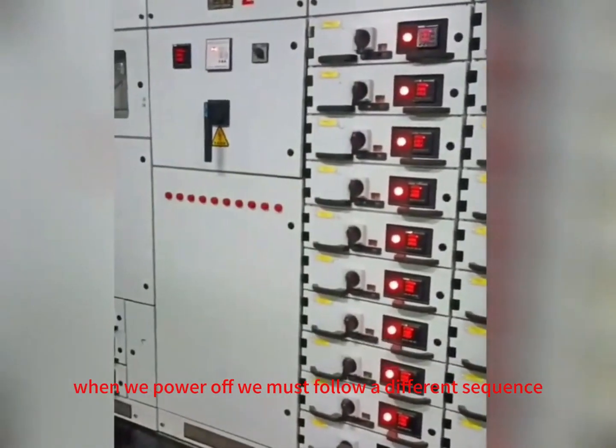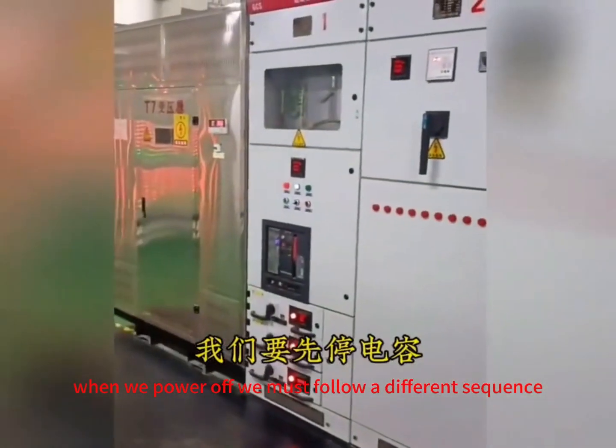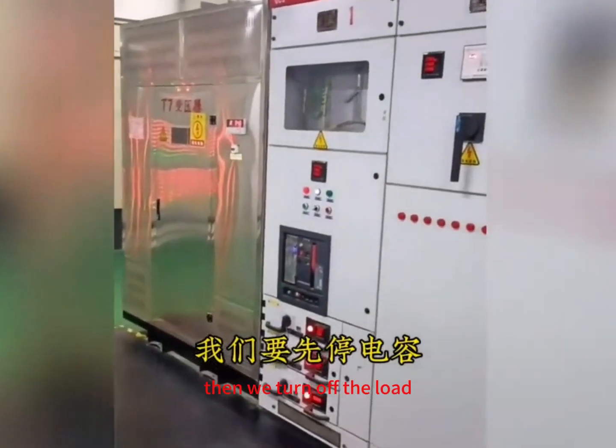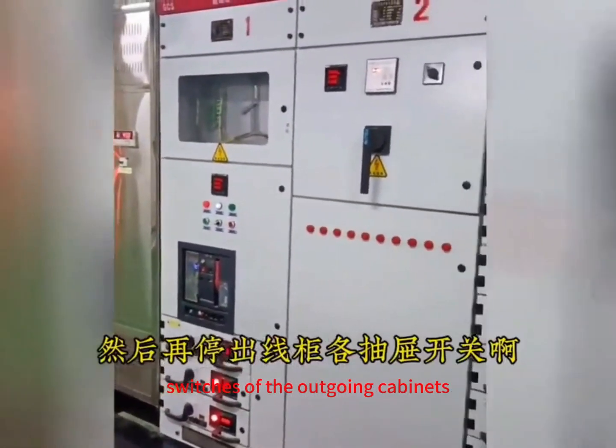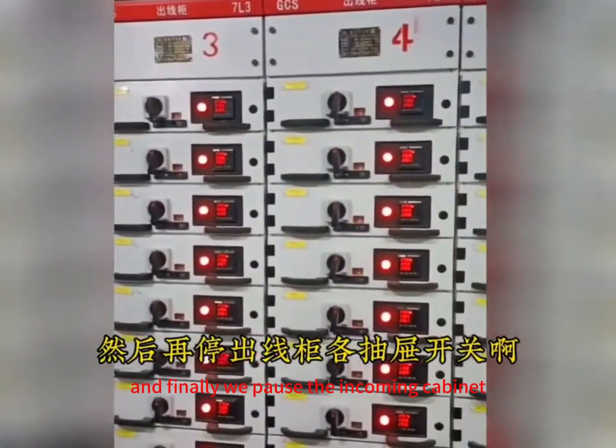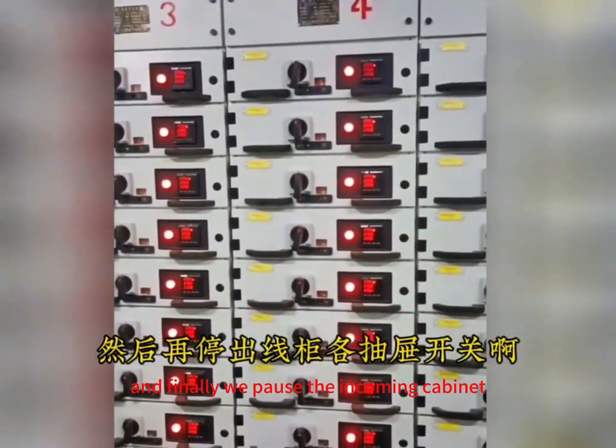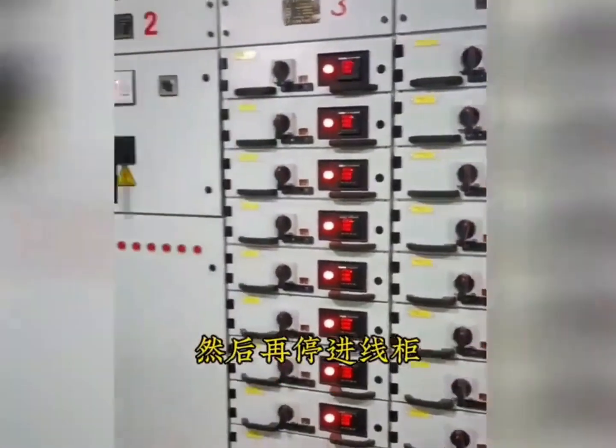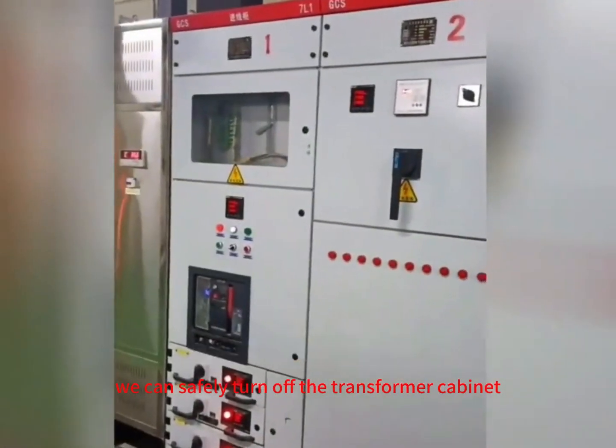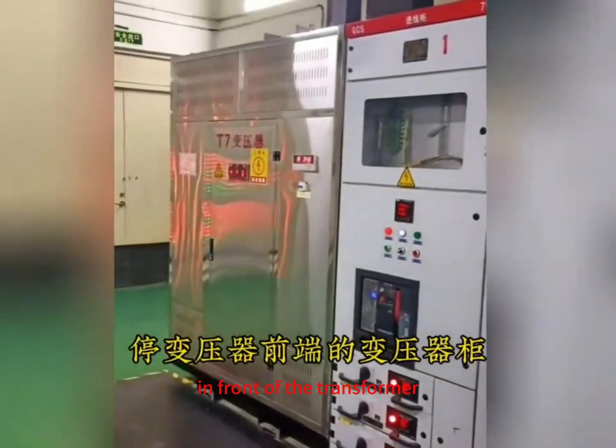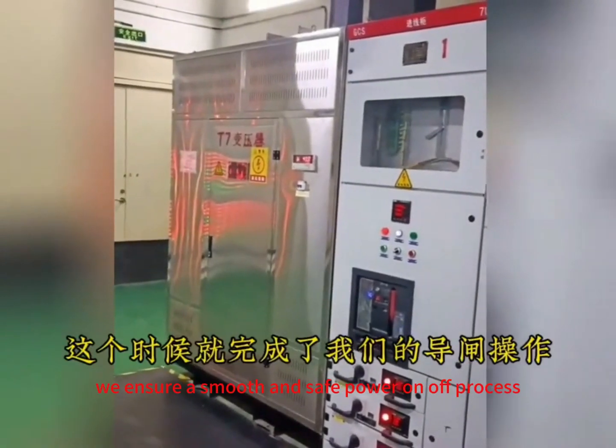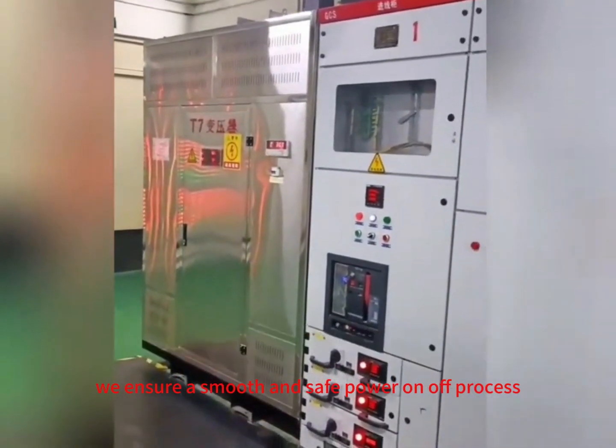When we power off, we must follow a different sequence. First, we turn off the capacitor, then we turn off the load switches of the outgoing cabinets to shut off the loads, and finally, we pause the incoming cabinet. Once the incoming cabinet is cleared, we can safely turn off the transformer cabinet in front of the transformer. By following these steps, we ensure a smooth and safe power on-off process.